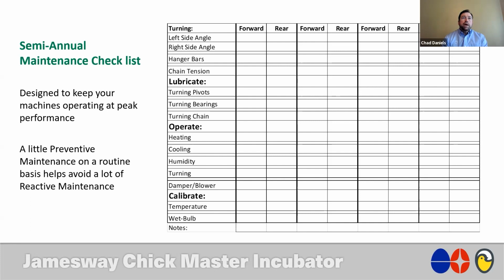So once we get past that, what we try to focus on a little bit is to physically force or operate the functionality of the machine, such as the heating, cooling, humidity, turning, and then a damper, or if it also has a blower, to actually force that blower to operate and make sure that it does the right thing. So it's important to process through those things, because a lot of times you'll see one of those functions not operating correctly, and it's a good time to double check all those things semi-annually.